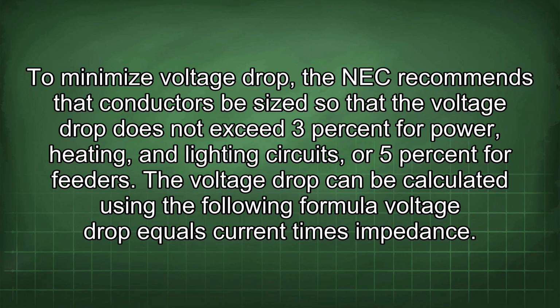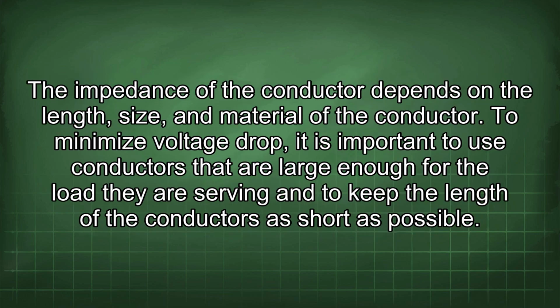The voltage drop can be calculated using the following formula: voltage drop equals current times impedance. The impedance of the conductor depends on the length, size, and material of the conductor. To minimize voltage drop, it is important to use conductors that are large enough for the load they are serving and to keep the length of the conductors as short as possible.